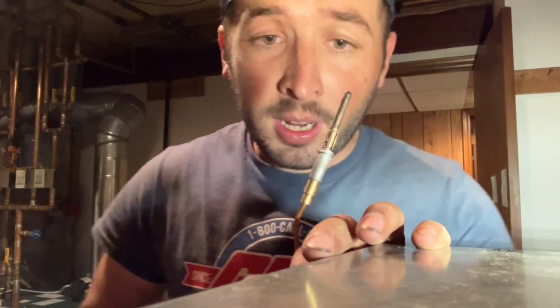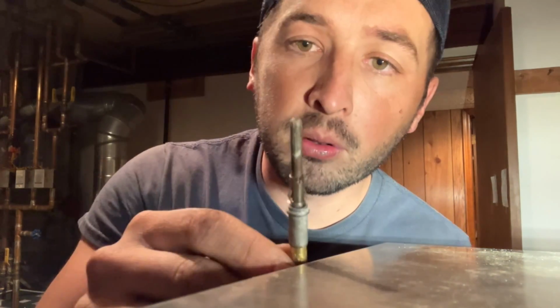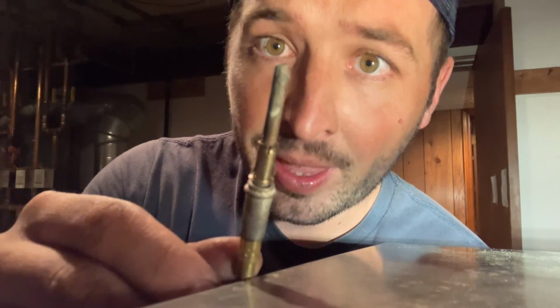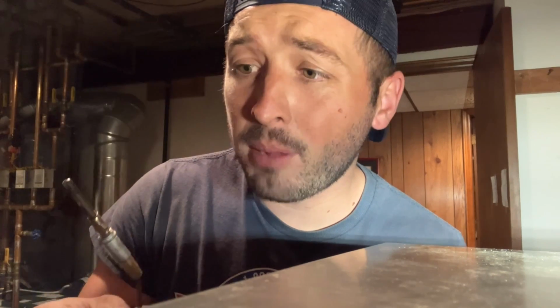Okay, here's a perfect example. Look at this thermocouple. Was it still working? Yes. Is it worth keeping? No, of course not. Fix the problem while it's small. This is gonna go out at some point. Will we get through the winter? I don't know, maybe. Is it worth taking the risk that the heat goes out in the middle of winter and we have to come back on a service call? I'm already here doing the maintenance, you might as well swap it out.